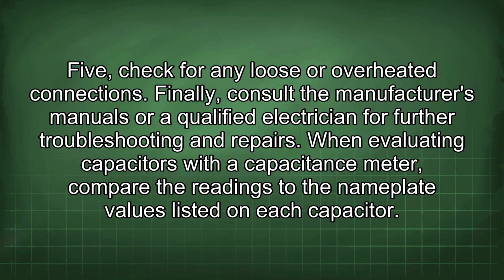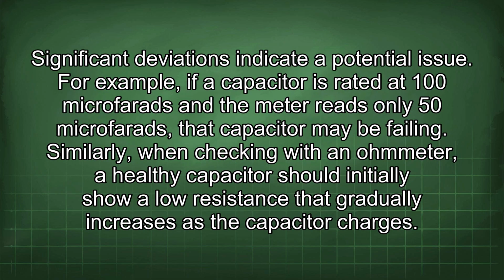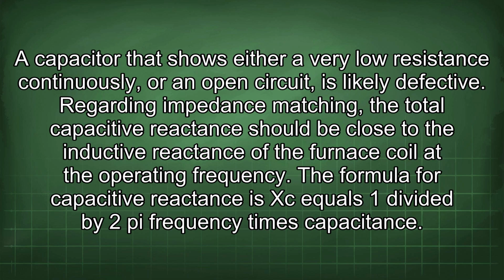When evaluating capacitors with a capacitance meter, compare the readings to the nameplate values listed on each capacitor. Significant deviations indicate a potential issue. For example, if a capacitor is rated at 100 microfarads and the meter reads only 50 microfarads, that capacitor may be failing. Similarly, when checking with an ohmmeter, a healthy capacitor should initially show a low resistance that gradually increases as the capacitor charges.